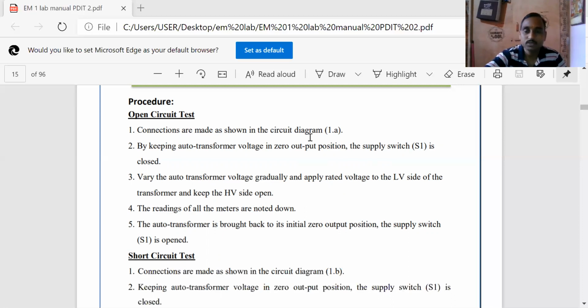Connections are made as per the circuit diagram, keeping the auto transformer voltage in the zero output position. Initially the auto transformer is in zero position, then you gradually increase it. Switch on the supply, then vary the auto transformer voltage gradually and apply the rated voltage. What is the rated voltage of the transformer? That is given in the nameplate details of the transformer. It is a single phase transformer, so obviously it is 230 volt. You apply 230 volt and give the supply voltage.